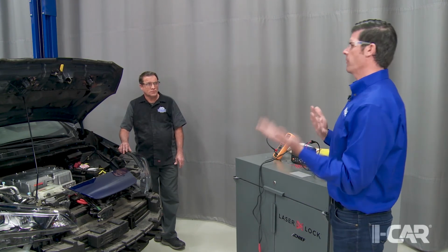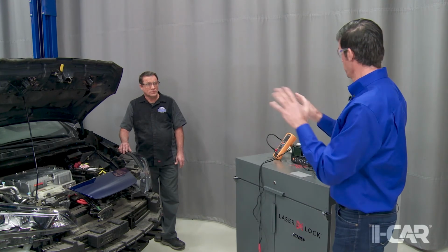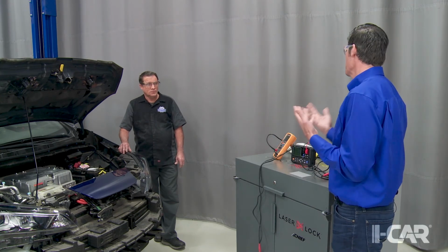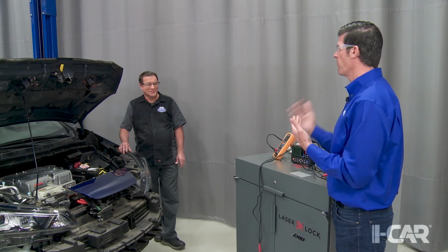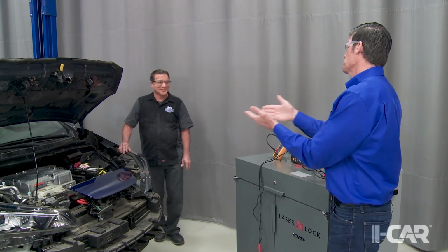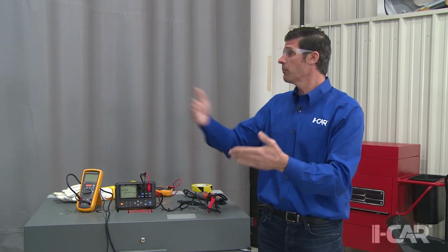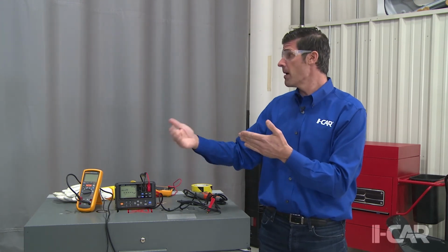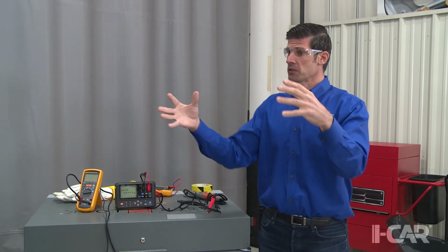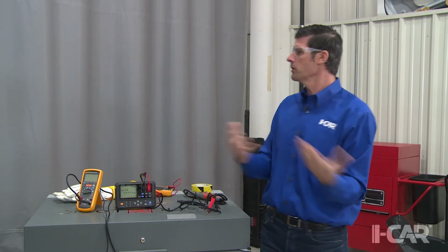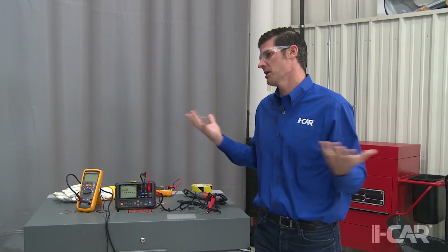Now, I'm European, and we have our regulations. In this European regulation, what's pretty cool - and that's why I like regulations - is it also defines what's supposed to be there. That 1 meter or 3 feet per milliohm is one number in that regulation, and the whole system, every component, should be under 100 milliohm. So now we have a guideline and we know what is good and what is bad, and that's what I need as a technician to know.